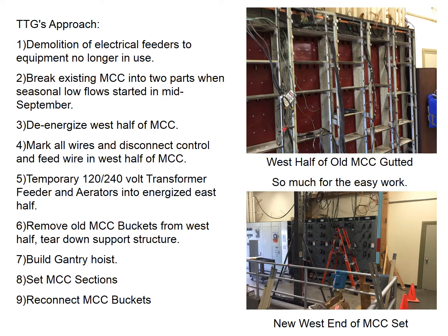TTG's approach to the project included: number 1, demolition of the electrical feeders to the equipment no longer in use. 2, break the existing MCC into 2 parts when seasonal low flow started in mid-September. 3, de-energize the west half of the motor control center. Number 4, mark all wires and disconnect control and feed wire in the west half of the MCC. Number 5, temporary 120-240 volt transformer feeder and aerators into the energized east half. Number 6, remove the old motor control center buckets from the west half, tear down the support structures.